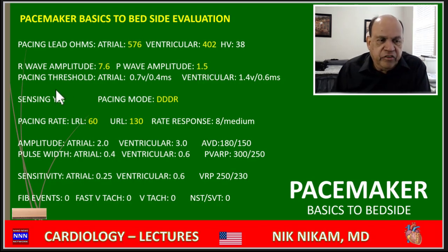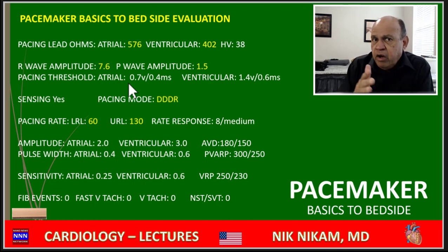We got pacing threshold. Remember I showed you those pacing thresholds? If it's 1.5, it was pacing 100%, 1.0, 100%, 0.5 volts miss the beats. And this is what it's saying. At 0.7 volts, at 40 milliseconds, it can pace the atria 100%. And same thing with the ventricles, it's double the energy and 60 milliseconds.